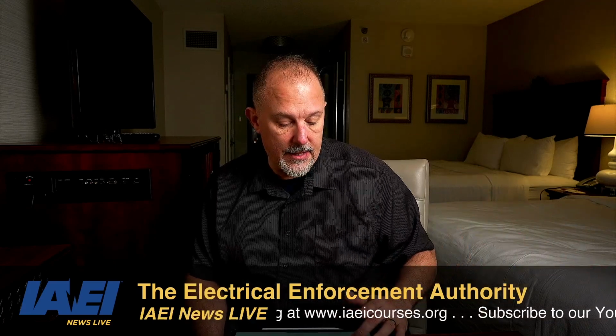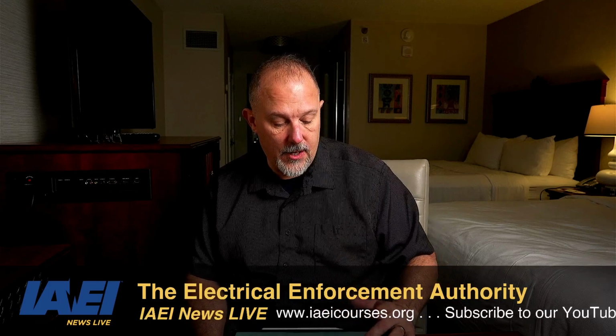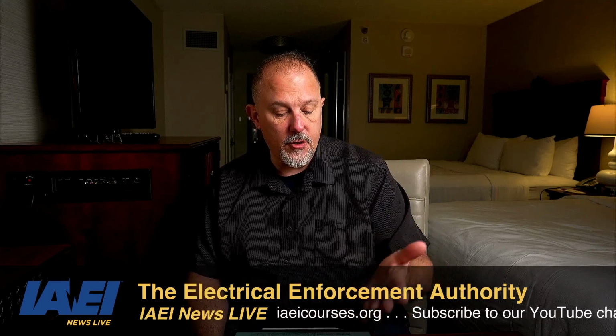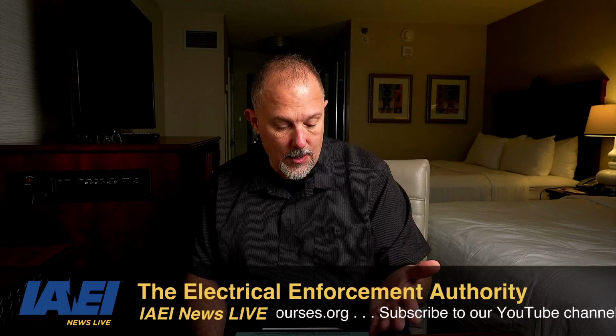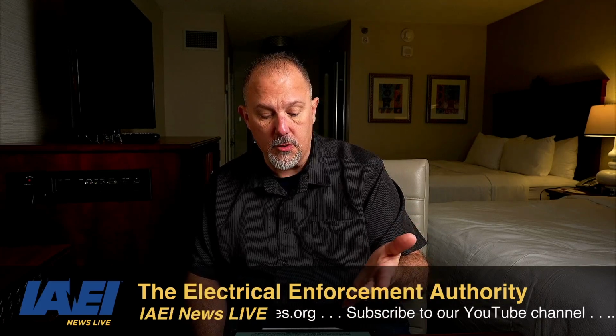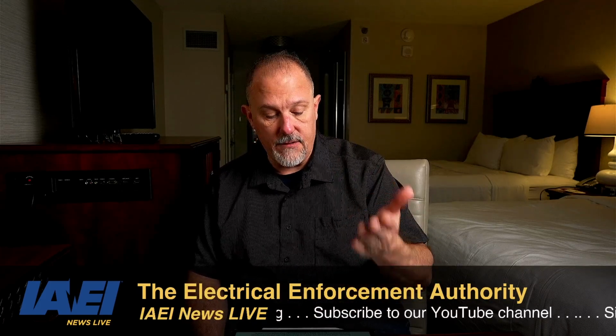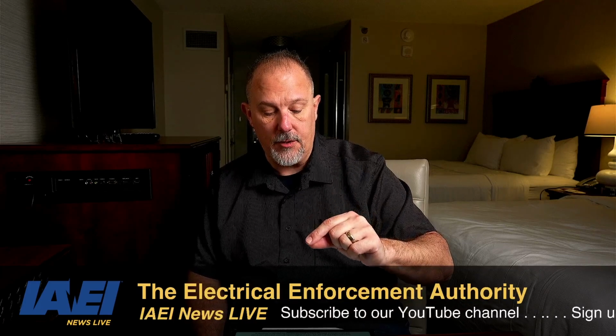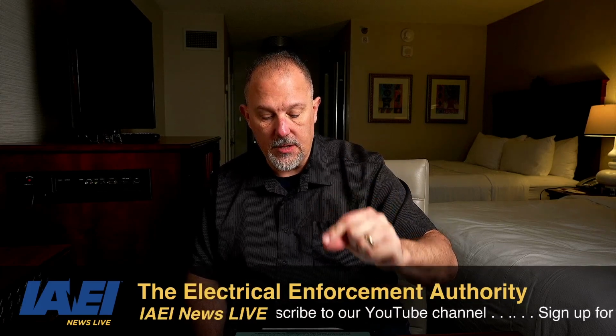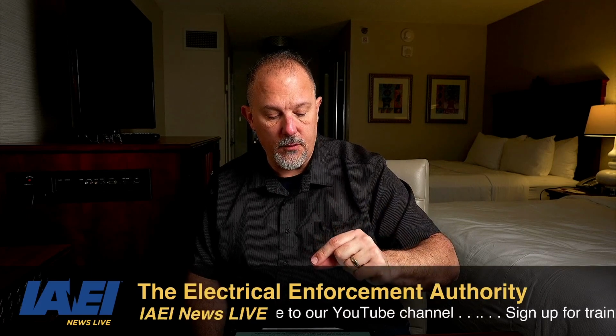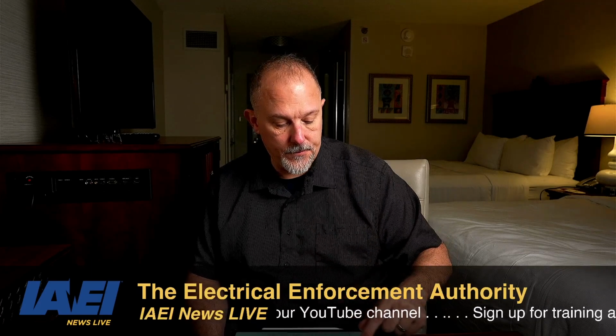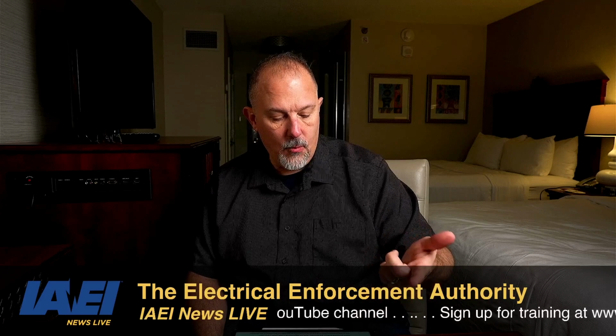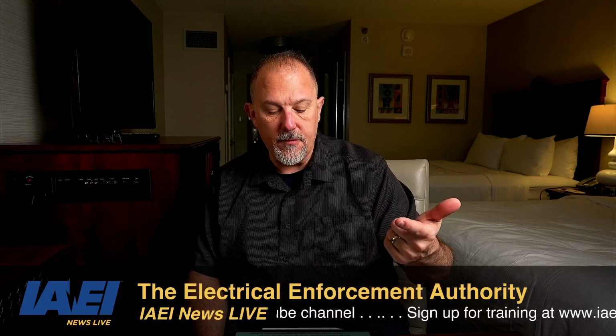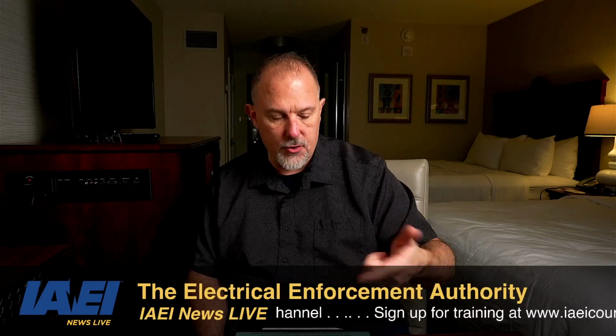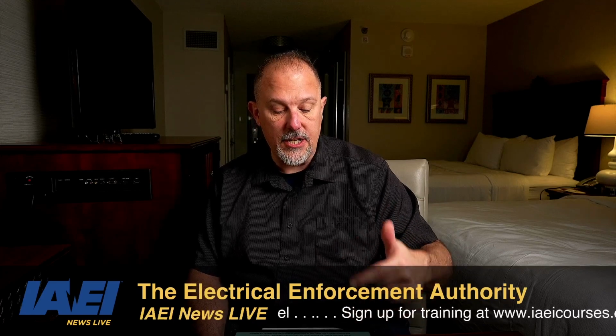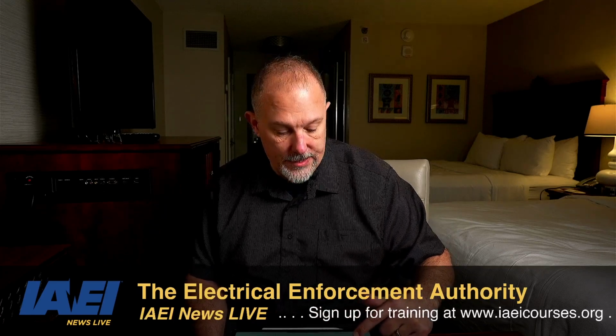That's, I think they rearranged this section as well and added some new requirements. You have emergency shutdown in one and two family dwelling units for other than cord and plug connected portable generators. An emergency shutdown device shall be located outside the dwelling unit at a readily accessible location and shall also meet the requirements of 445.19(A)(1) and (2). A1 is be equipped with provisions to disable all prime mover start control circuits, and A2 is initiate a shutdown mechanism that requires a mechanical reset.